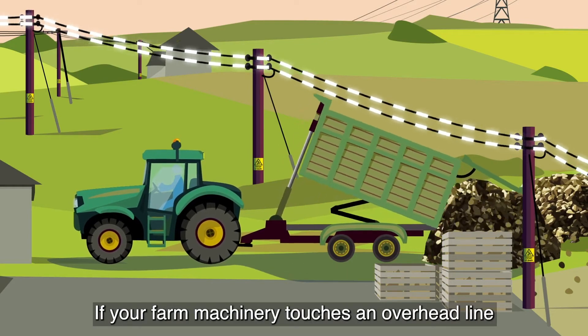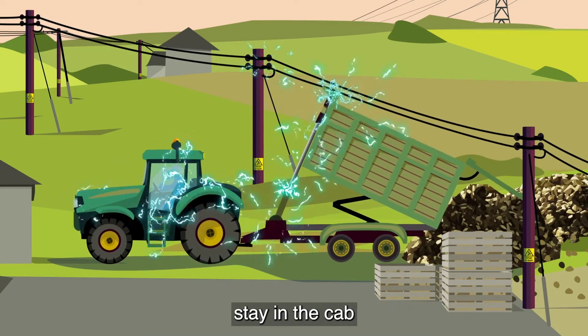If your farm machinery touches an overhead line, stay in the cab, call 105, wait for assistance, and always assume lines are live unless the distribution operator tells you otherwise.